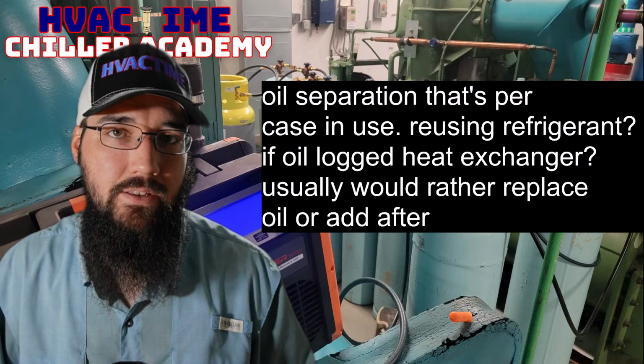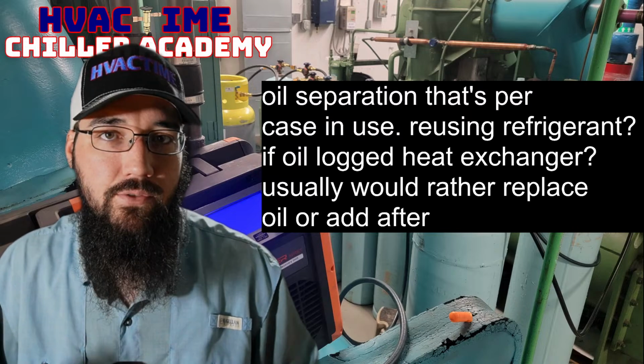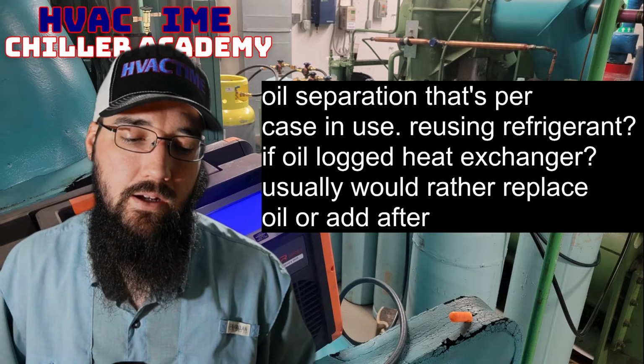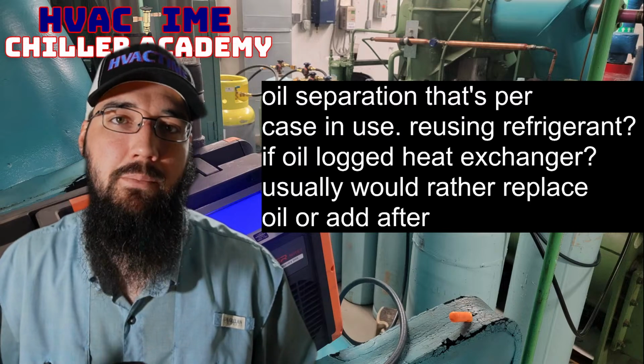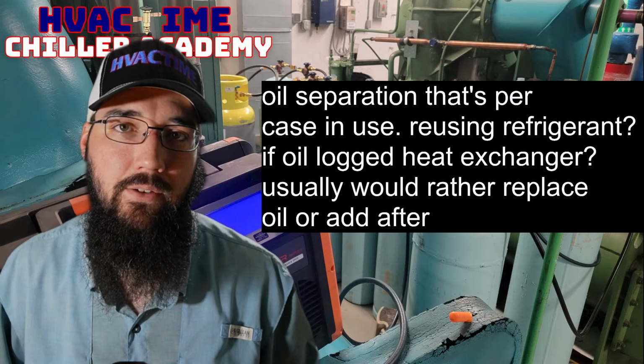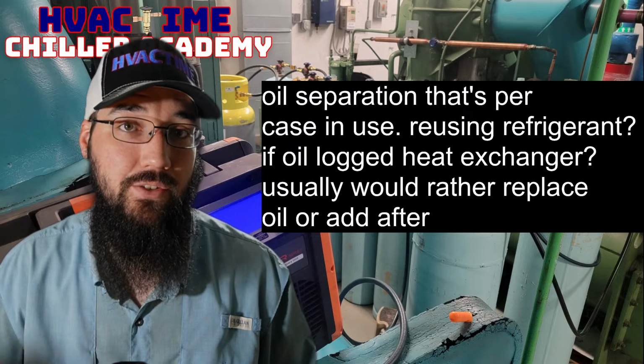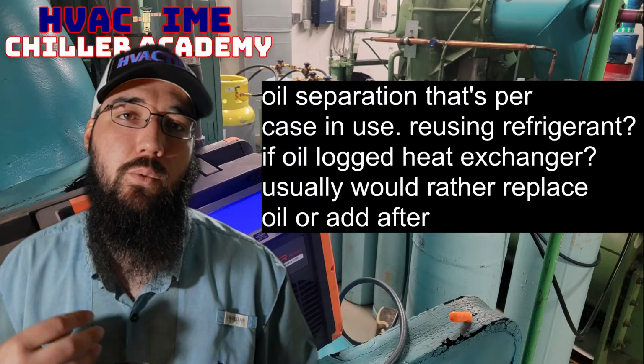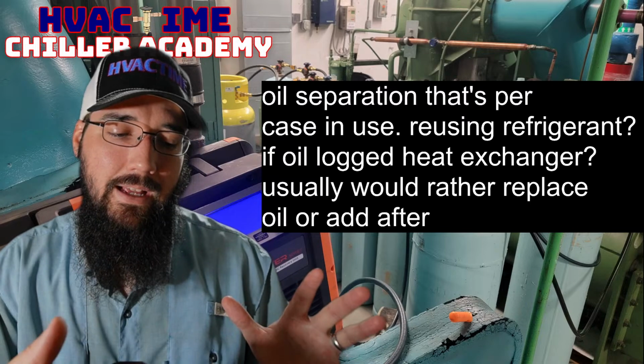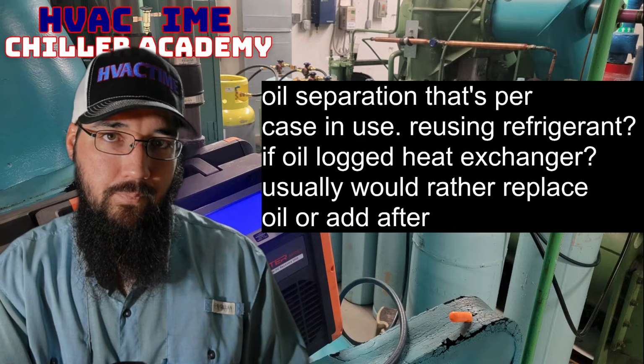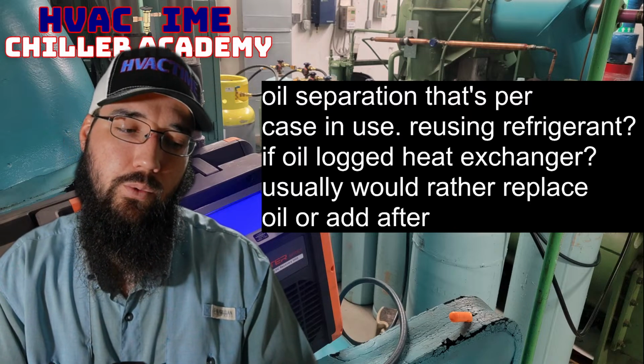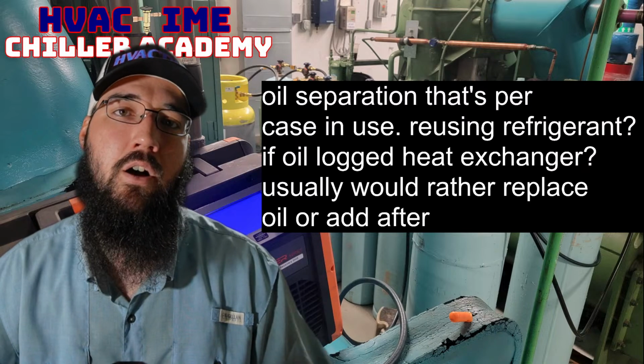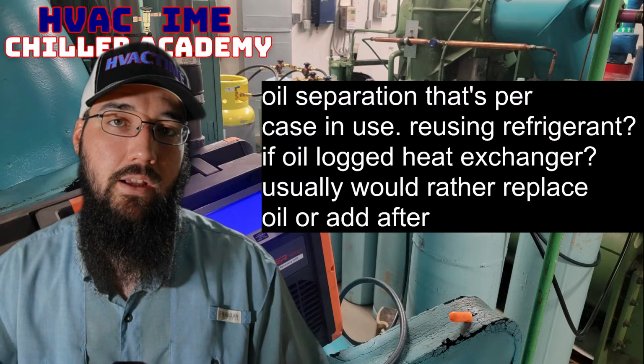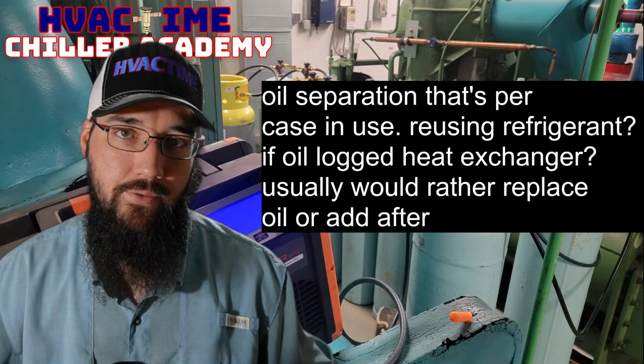Now, if you can get the machine online, even if just for a short time, try to get some of that oil back. A way to do that, if you're in a situation with a severe migration event, is I'll add just enough oil into the sump to allow the machine to come online safely. Just enough oil.